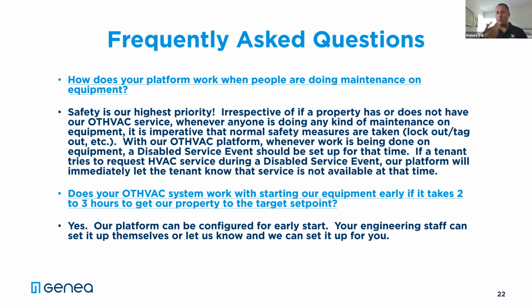We can do early start as well. So to the earlier question about how long it takes for a building to get comfortable - that depends on mechanically how the building is set up. We'll leverage the knowledge of your building engineering staff to understand, when a request is for Saturday to get to comfort, when do we have to turn the building on. If it's an hour, if it's 2 hours - in some parts of the country, certain times of year we have to turn on 4 hours early. In other parts, especially during August when it's ridiculously hot, it makes more sense to run the buildings 24/7 at a bare minimum load. After that, it's just ramping up to new floors, turning on fans and air handlers as appropriate.